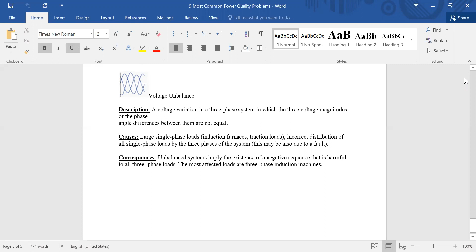What are the causes? A large single phase load, such as induction furnaces or traction loads, or improper distribution of single phase loads in a three phase system. This may also be due to a fault. These are the causes for voltage unbalance. As for the consequences, an unbalanced system implies the existence of negative sequence, which is harmful for three phase loads. The most affected loads are three-phase induction machines.